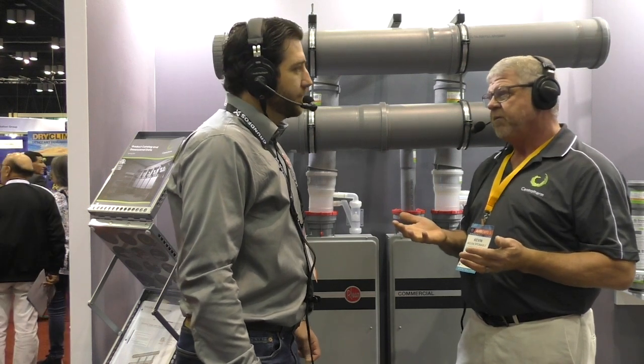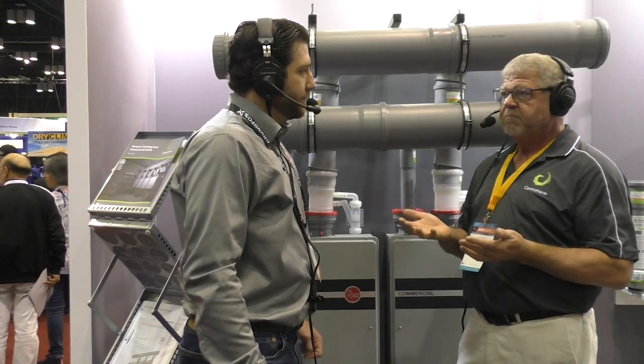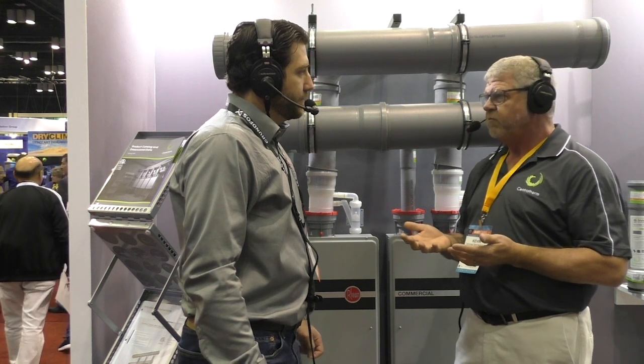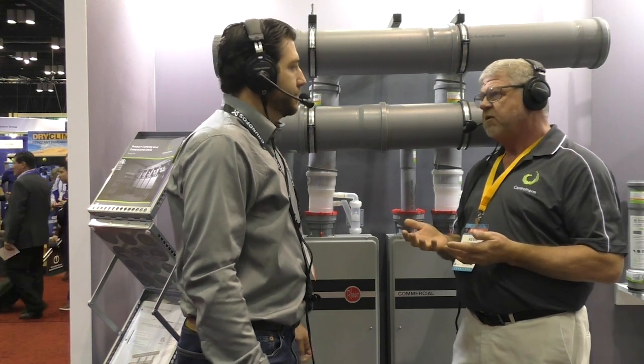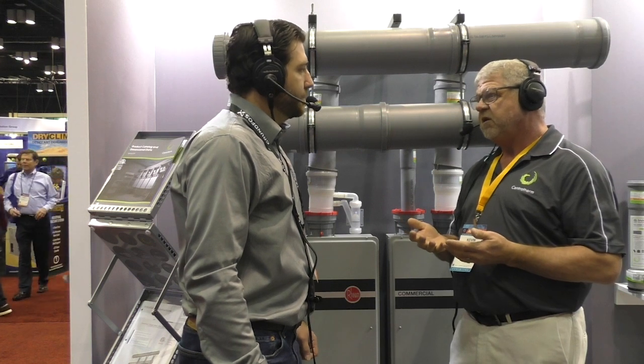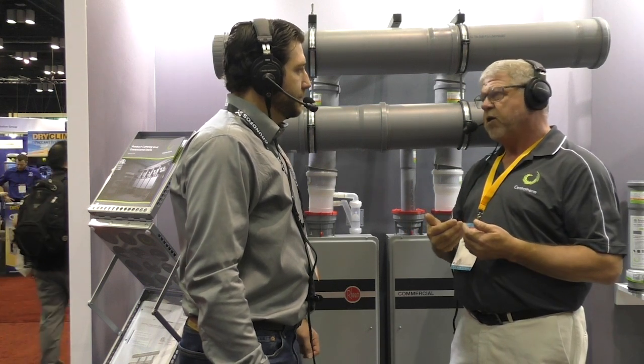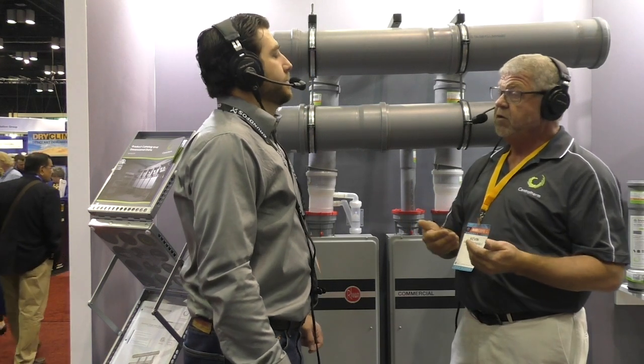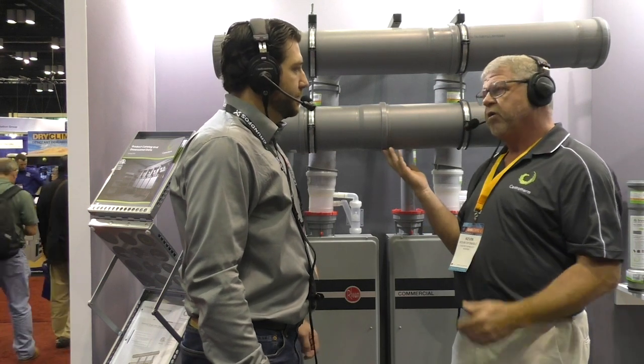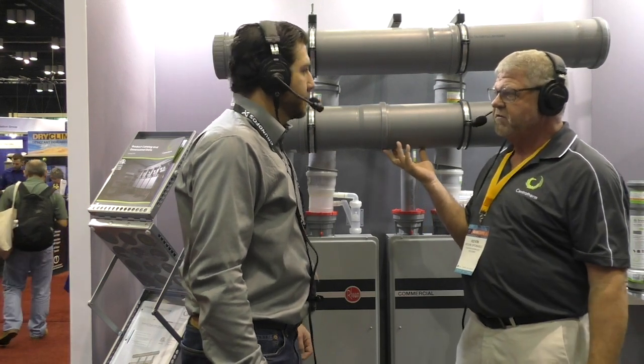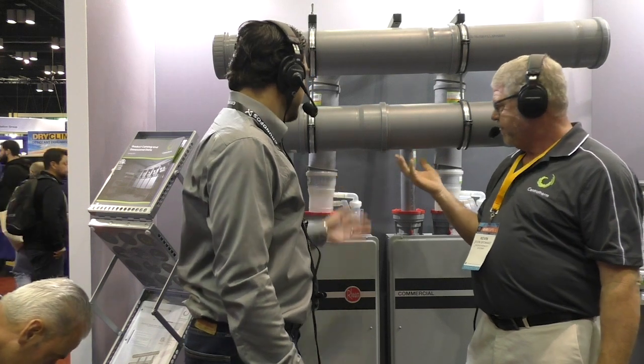The biggest thing for PVC and CPVC is they're rated for wastewater. If you go into the ASTM standards for PVC and CPVC, it specifically states that this product is only designed for wastewater, and if you're going to use a product for flue gas, you should use a product like this, which is UL 1738 listed. It's a great product.